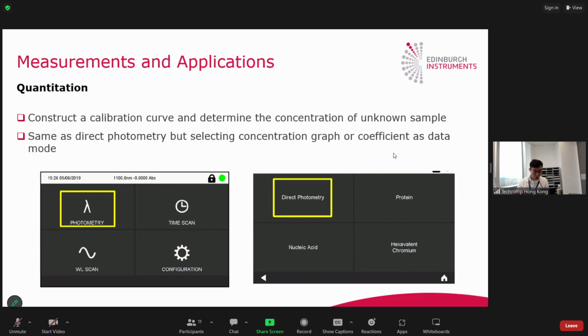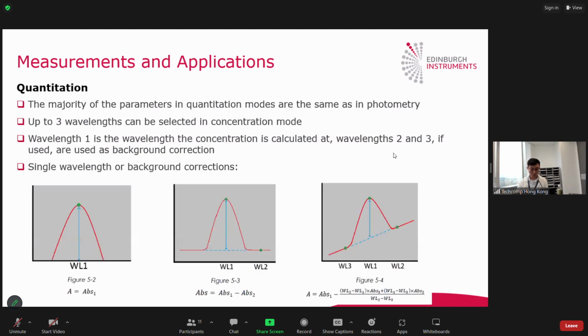For the quantitative analysis, it is used to construct a calibration curve and then determine the concentration of the unknown sample. Basically, this quantitative analysis is the same as the direct photometry, and you can also select direct photometry here for measuring the quantitative analysis, but you need to select the concentration graph and also the concentration coefficients as the data mode. The parameters will be the same as in the photometry.